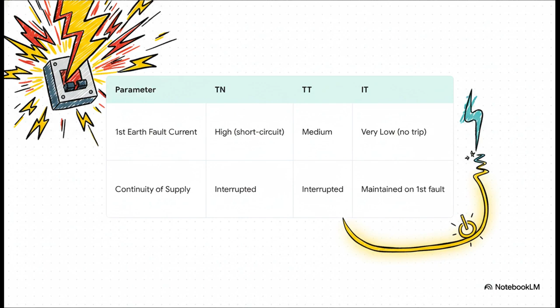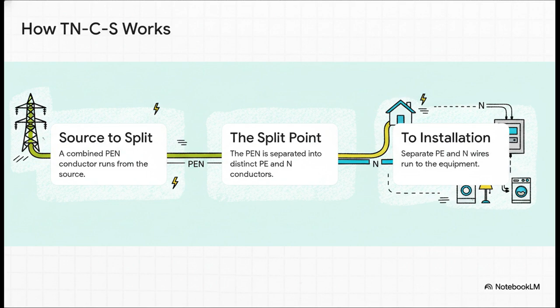So to make this a little more real, let's look at probably the most common setup in the world, the TNCS system. You start with that combined PEN wire coming from the utility. Then, at your building's main electrical panel, that wire gets split. From that point on, you have a totally separate protective earth wire and a separate neutral wire running out to all your outlets. It's a really clever and practical compromise. But here's the thing. An earthing system is just a path. It's a road. It can't actually do anything on its own. It needs a partner, a device that can see the fault and slam on the brakes.